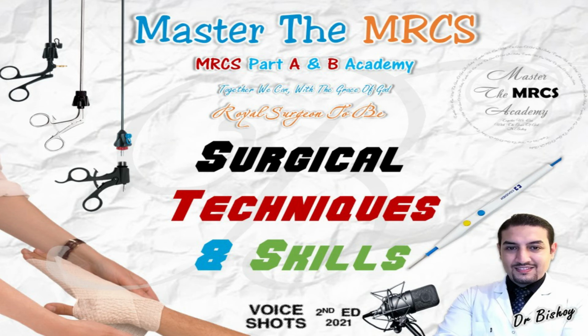Regarding the ligature device, it delivers a tailored energy level to allow simultaneous hemostasis and dissection at the same time. The device senses the impedance of the tissue and tailors the energy level accordingly. And almost always you have to take care of the hazards that can be caused by the diathermy, either the monopolar or the bipolar. Of course, most of the plastic surgeons require precision by the bipolar. Even they use now the needle, not only the bipolar. And the bipolar is the electric current flowing from one electrode to another. However, both electrodes are usually contained within the same device, a pair of forceps. It's like a forceps. Yes, very stylish to use a bipolar.